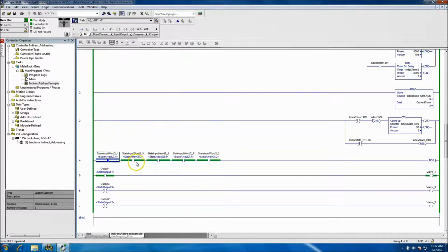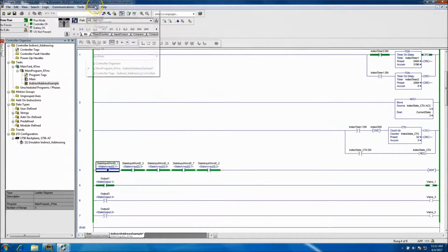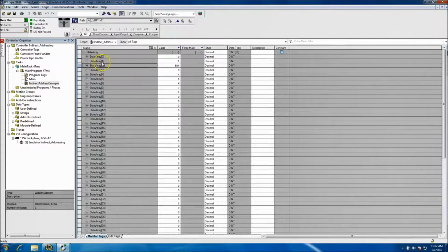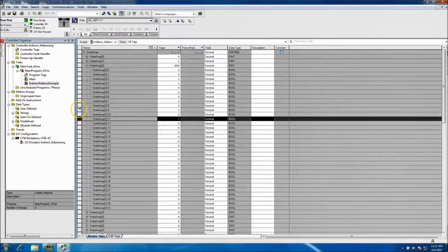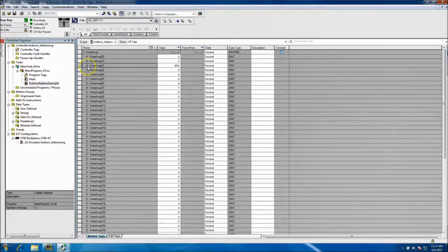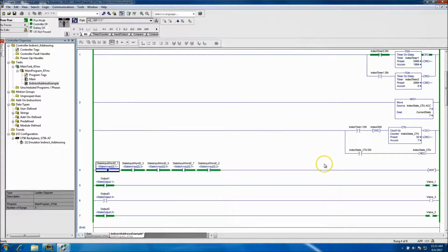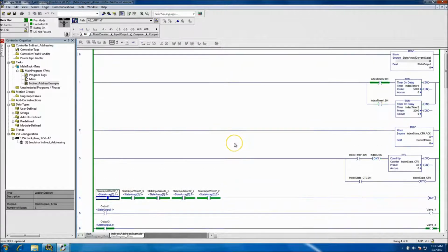That's basically the input word, right? So what we're saying is, with the indirect address of whatever array we want, we're cutting on either this bit, this bit, or this bit, whatever bit you want to choose. You can cut on and use it for whatever you want at that point in time. You can make this as big and elaborate as you want. This is just a really simple, cut and dry method to do this, and you can have this do multiple things. We use it for a good state machine, so state 1 would do this, state 2 would do this, many different aspects, right?